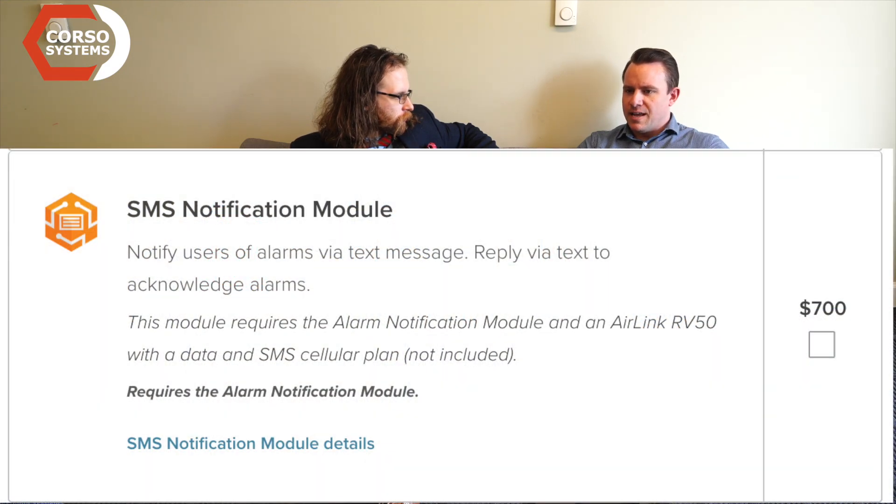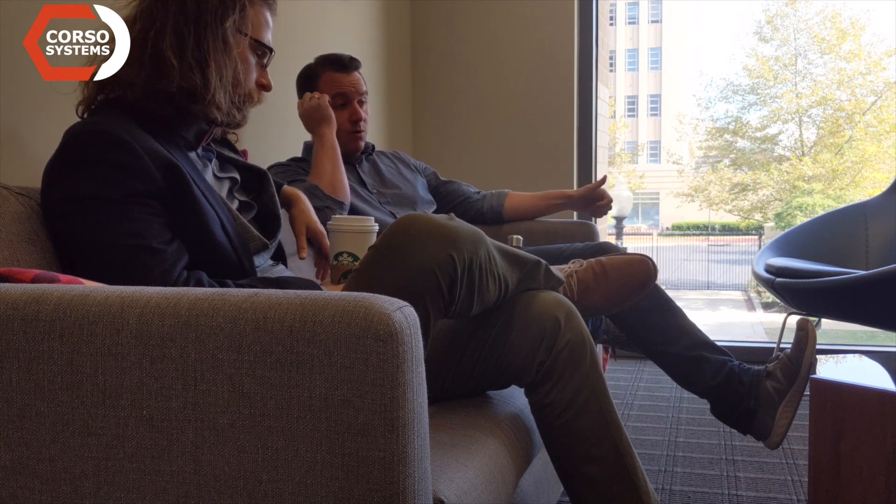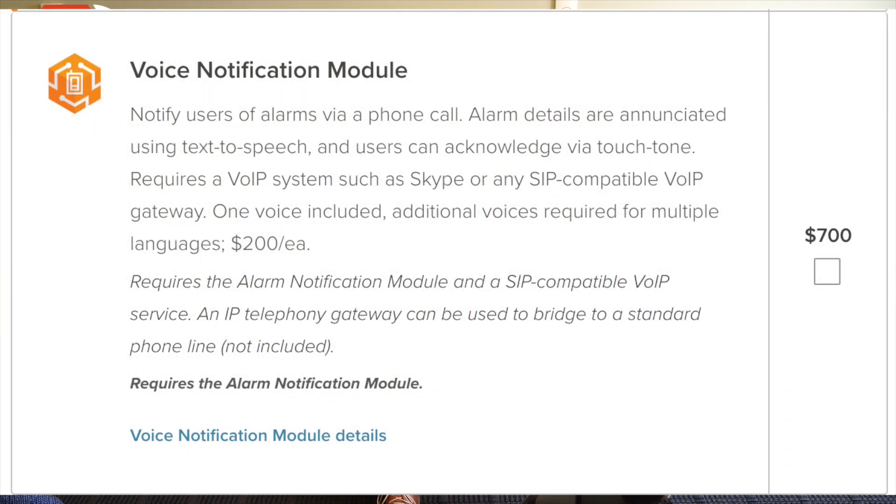Personally, unless you already have an SMS modem in your plant that you're migrating from, I would just go with the Twilio module — that's what we use. The benefit of the Twilio module is it gives you both phone capability and SMS capability. It does add a second system to worry about, but you don't really need to know much beyond setting up an account, and Twilio is pretty solid — it's a couple of cents per text message. The voice notification module will send you a phone call through the text-to-speech engine in Ignition, and you can pick different voices in different languages, which is pretty cool.